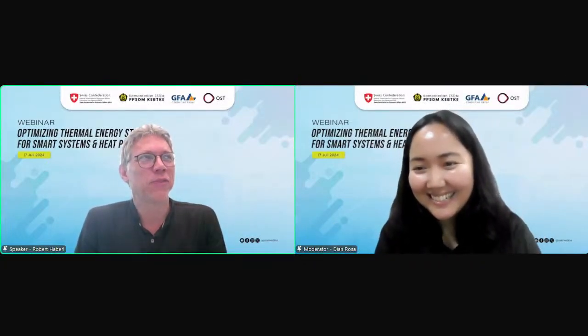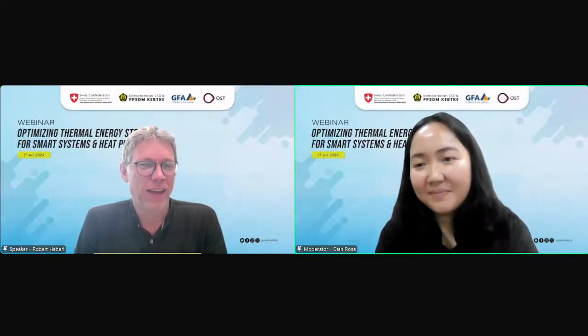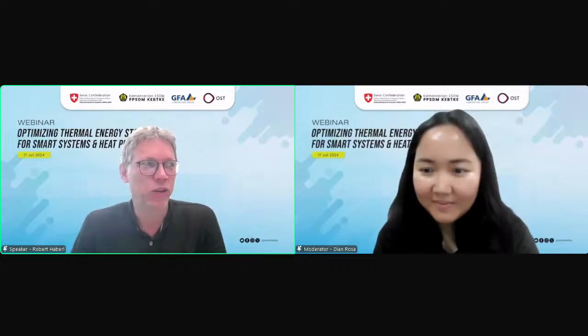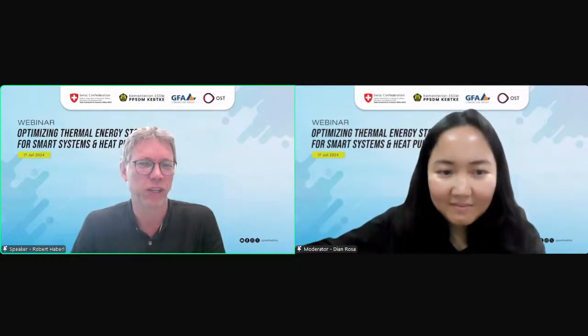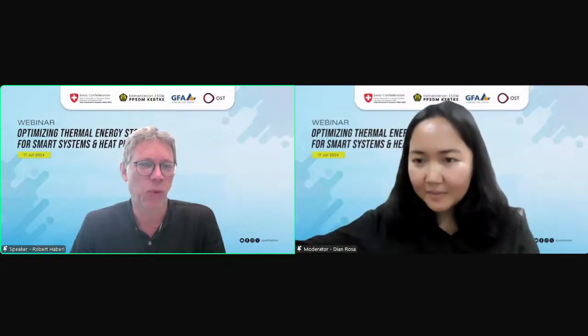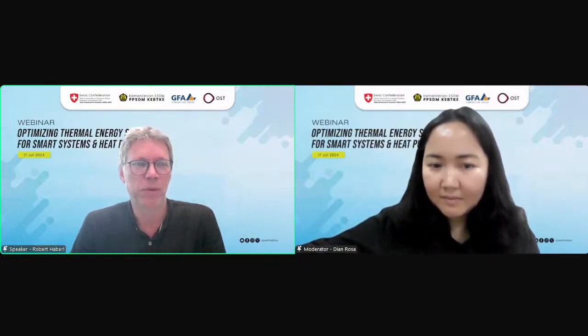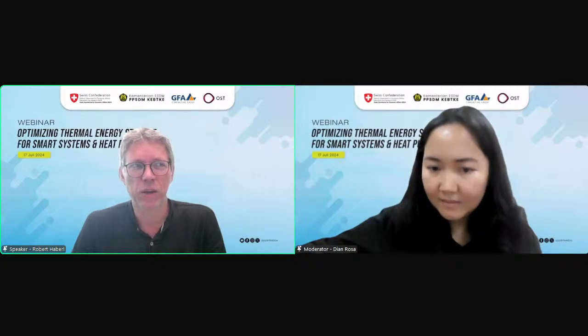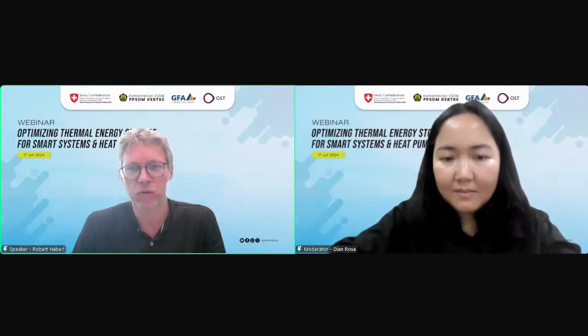Here we have a heating demand for space heating, and that demand is usually covered by heat pumps. That's nowadays the normal way of producing heat. So we have a heat pump anyway, and if there is a heat pump available in a residential building, it's most cost effective to use it also for domestic hot water preparation. That means the investment cost of the heat pump is needed to cover the space heating demand, and then it's also used for domestic hot water, in one device.